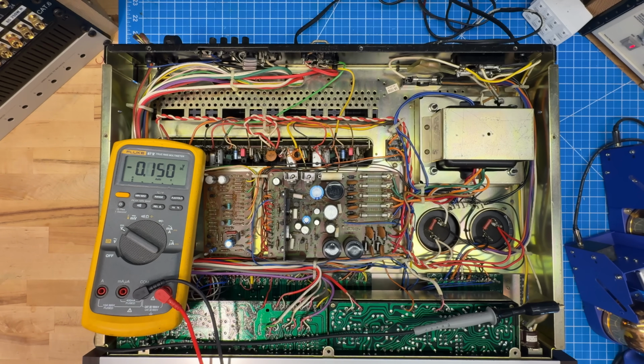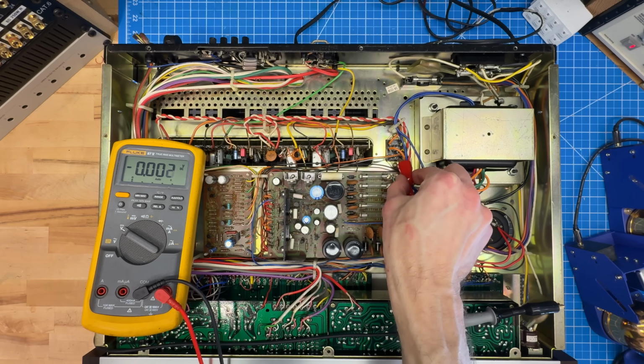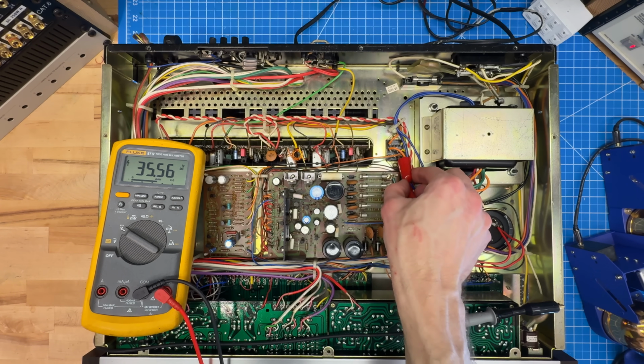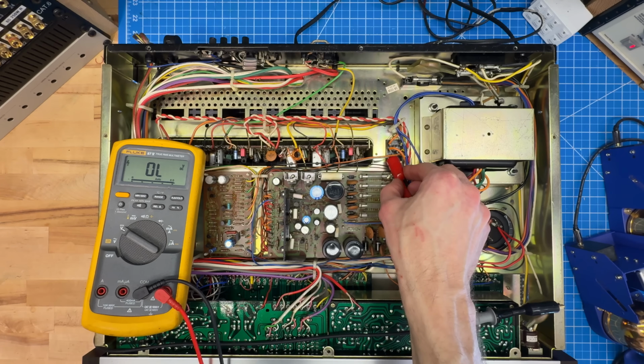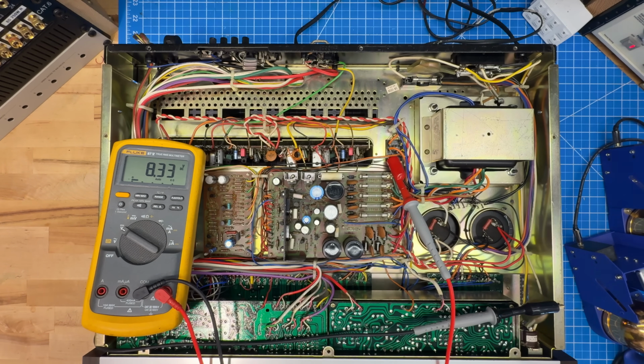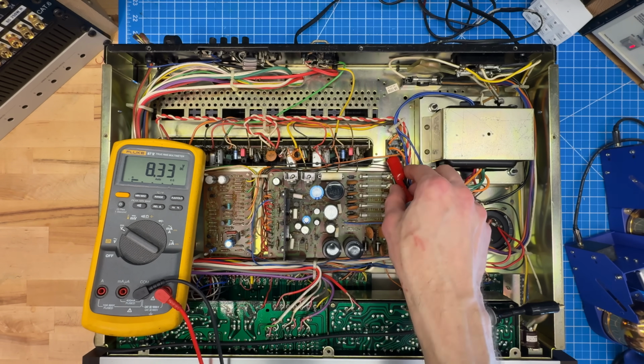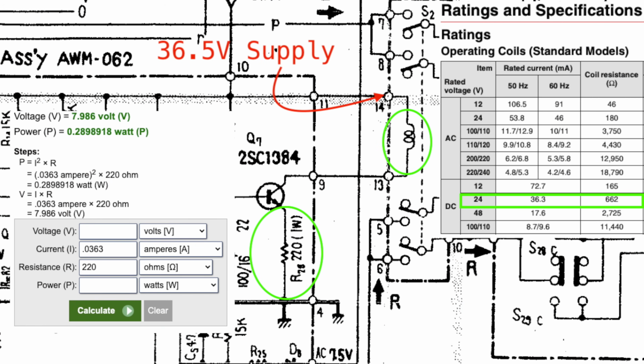This is going to be hard to diagnose until the relay fails again, but for now let's take a look at the supply voltage. With one hand behind my back, measuring 35.5 volts here and about 8.5 volts there. That might seem a little strange, but it's actually correct - this is a 24 volt relay, and 35.5 minus 8.5 is about 27 volts, so that coil voltage is actually just about correct.